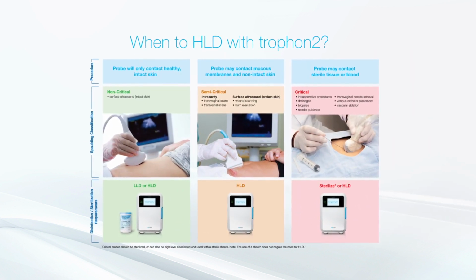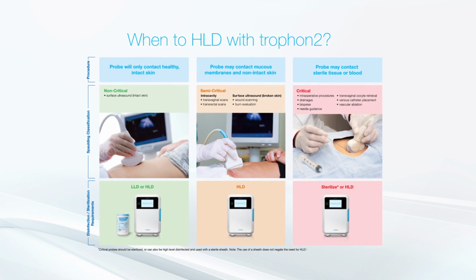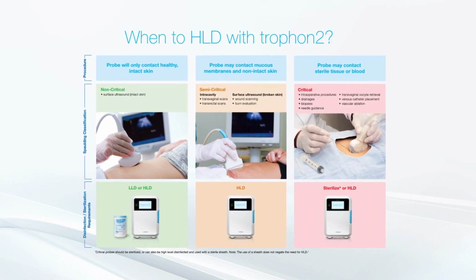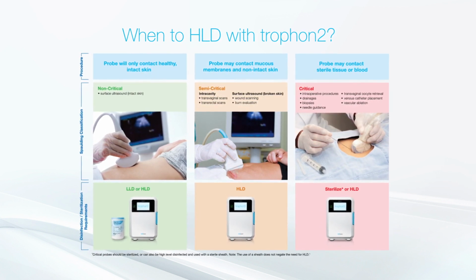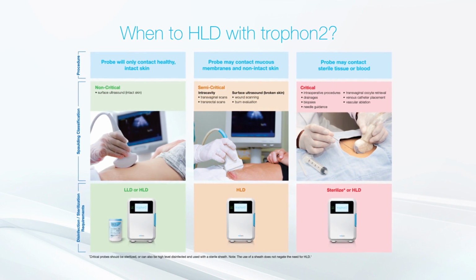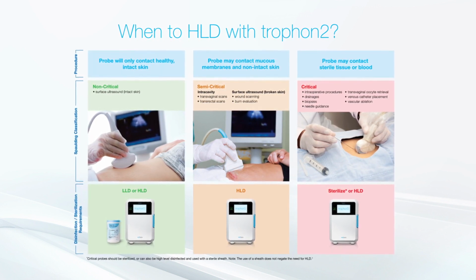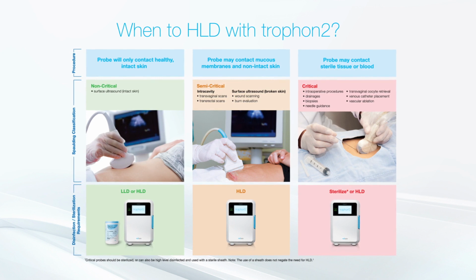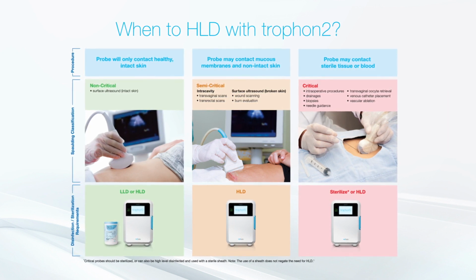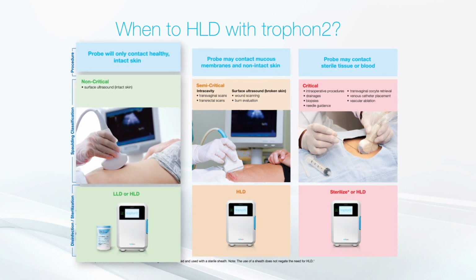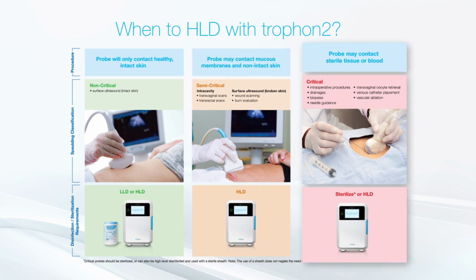To know when to perform high-level disinfection, refer to this diagram in the trophon2 Operation Training Guide or on the Nanosonics website. Applying the correct level of disinfection is based on the procedure the probe is going to be used for on the next patient, as defined by the Spalding classification: non-critical, semi-critical, critical.